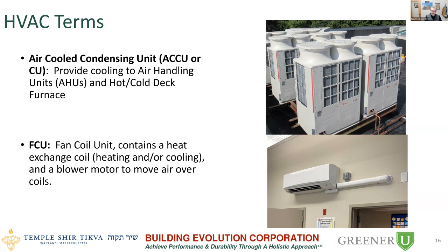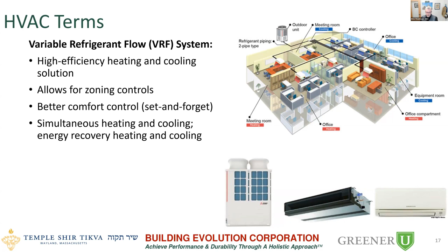And when you put the whole system together as a heat pump system, they're all variable flow. So it's a variable refrigerant flow, or VRF system. And that's where you have your outdoor condensing unit, that box that's sitting on the grade or on the roof of your building, and is connected with refrigerant pipes to your fan coil units indoors to provide the heating and cooling. And some types of VRF systems, like a couple of the systems at Temple Shir Tikva, have simultaneous heating and cooling, so that adjacent rooms could have heating or cooling, and that helps improve comfort in spaces. So a heat pump system is a temperature control system to help control comfort in spaces.